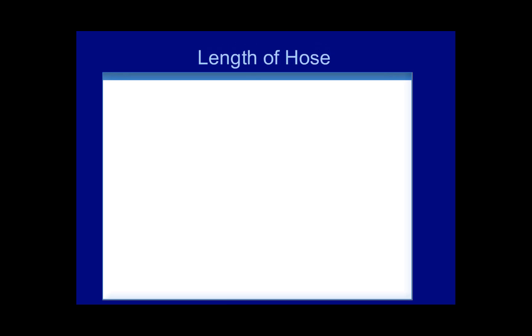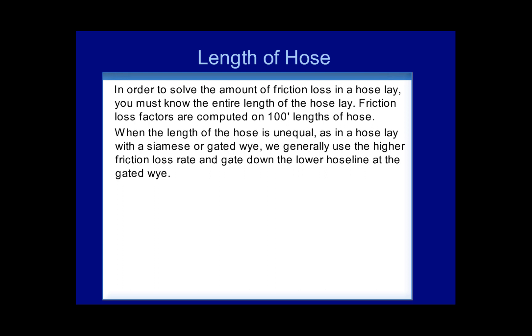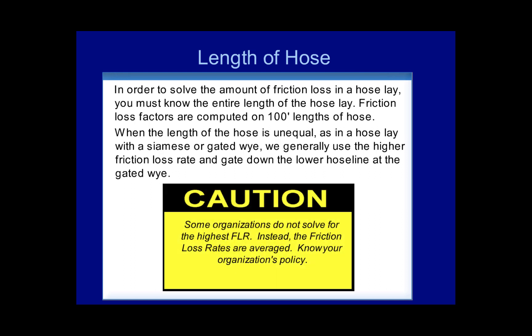Length of hose. In order to solve the amount of friction loss in a hose lay, you must know the entire length of the hose lay. Friction loss factors are computed on 100-foot lengths of hose. When the length of the hose is unequal, as in a hose lay with a Siamese or gated Y, we generally use the higher friction loss rate and gate down the lower hose line at the gated Y. Use caution: some organizations do not solve for the highest FLR; instead, the friction loss rates are averaged. Know your organization's policy.